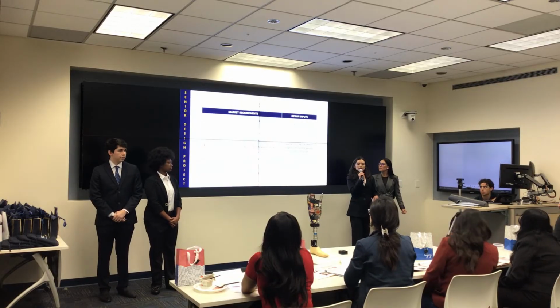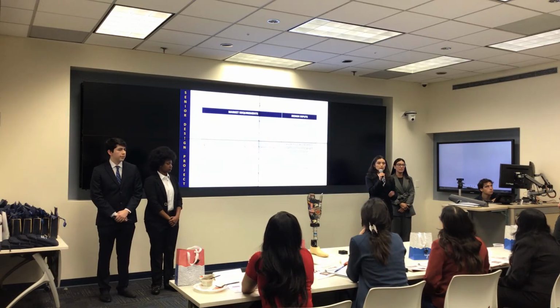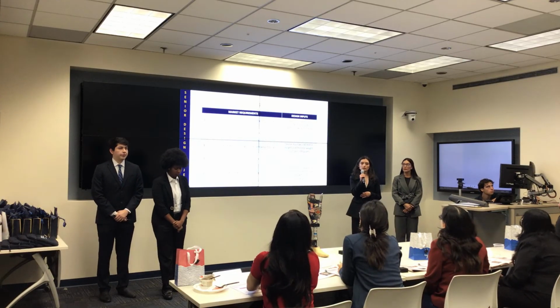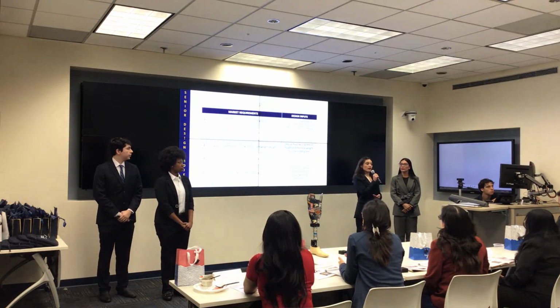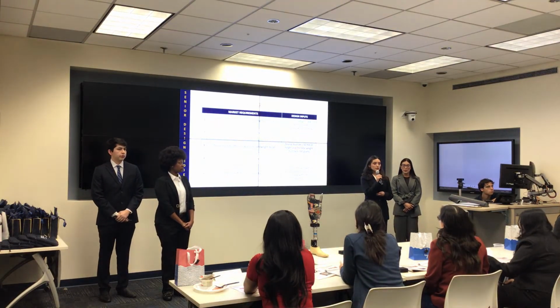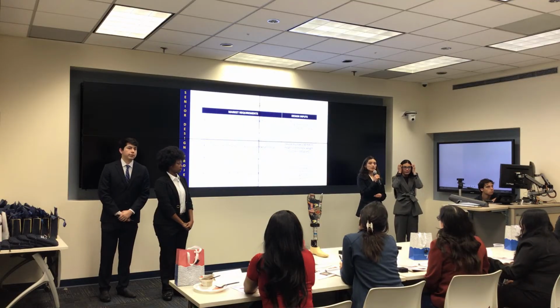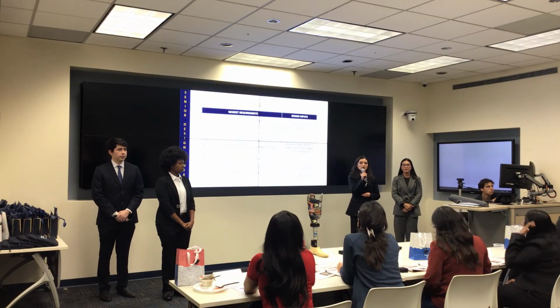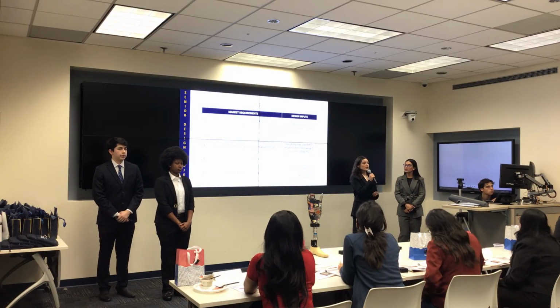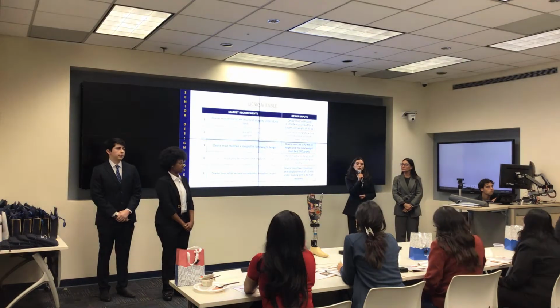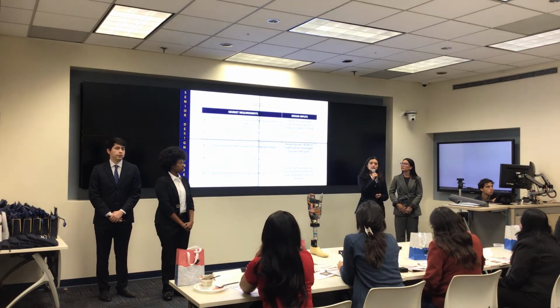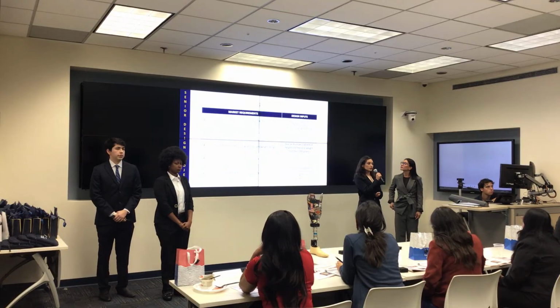To fill in the gaps in the market research and current modalities, we will be targeting the average user weight for transtibial amputees, which is 85 kilograms, meaning that our device must withstand up to 1,250 newtons of axial load. In terms of practicality, our device is lightweight and compact. So the total height must not exceed 50 millimeters and the total weight must not be greater than 300 grams.